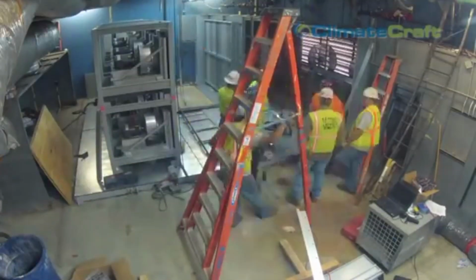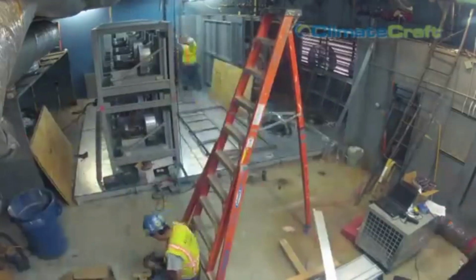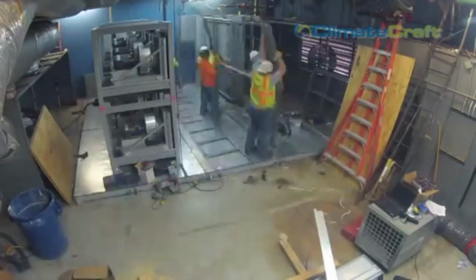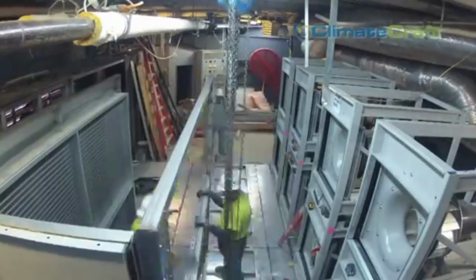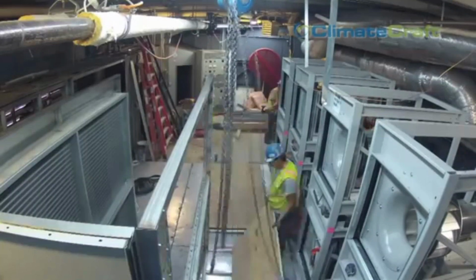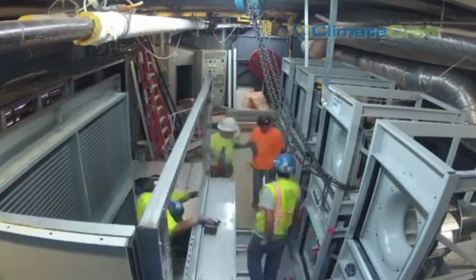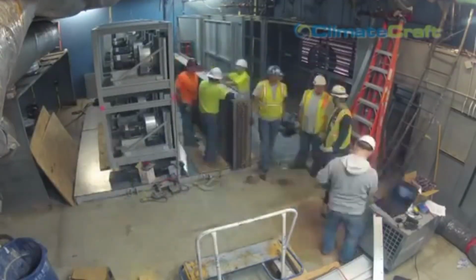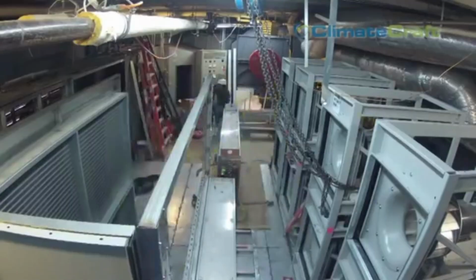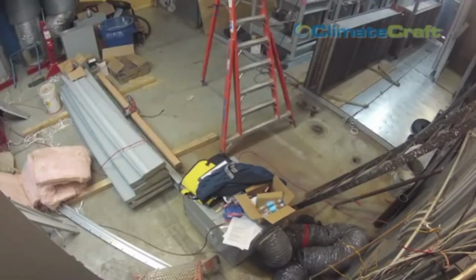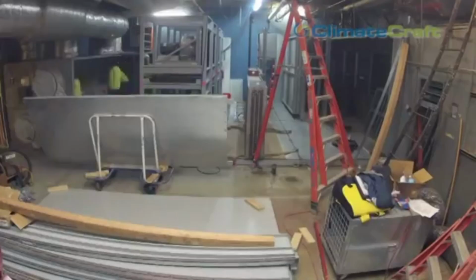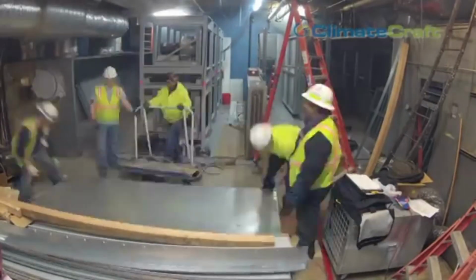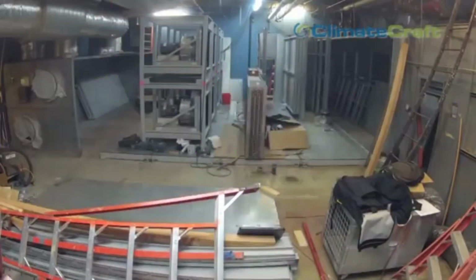ClimateCraft's fan matrix solution: if one fan fails, the other fans adjust to compensate for the shortage. This means the facility is less likely to have a sudden air handling unit shutdown due to a fan failure. Additionally, replacing this smaller fan would not require specialty equipment and a large contingency plan, since the replacement would simply involve carrying out the bad fan and installing a new fan in its place.